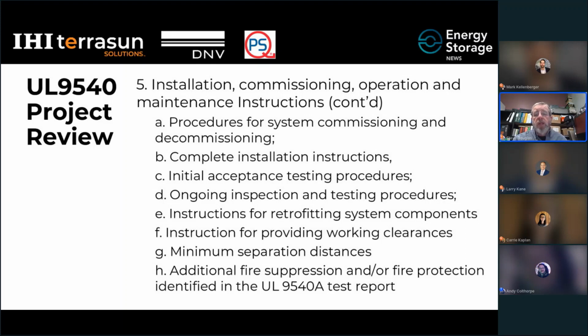The working space and clearances within the energy storage systems are covered within the standard itself for the components within the energy storage system, along with additional fire suppression and fire protection identified in UL 9540A test reports. So once, as Carrie was mentioning, those tests are done, that information is used when the analyses are done, and then it's included in the instruction manual. The other thing that is included in here is minimum separation distances between energy storage systems.